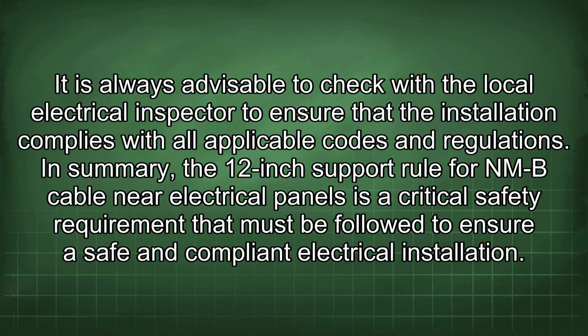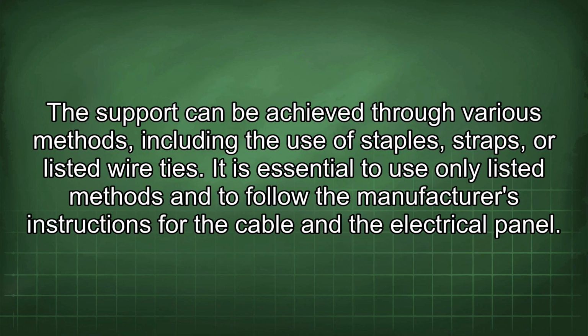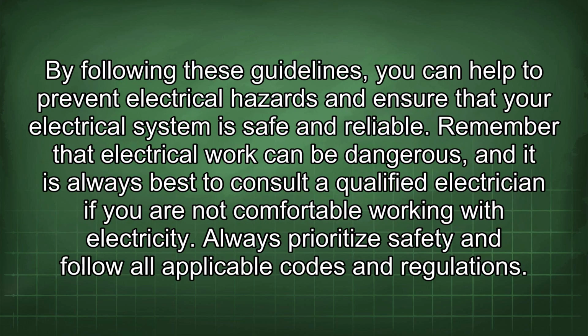In summary, the 12-inch support rule for NMB cable near electrical panels is a critical safety requirement that must be followed to ensure safe and compliant electrical installation. The support can be achieved through various methods, including the use of staples, straps, or listed wire ties. It is essential to use only listed methods and to follow the manufacturer's instructions for the cable and the electrical panel. By following these guidelines, you can help to prevent electrical hazards and ensure that your electrical system is safe and reliable.